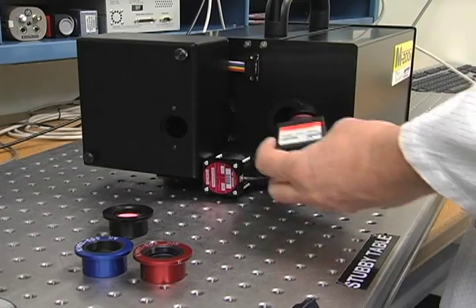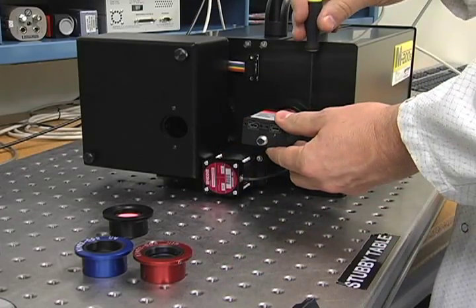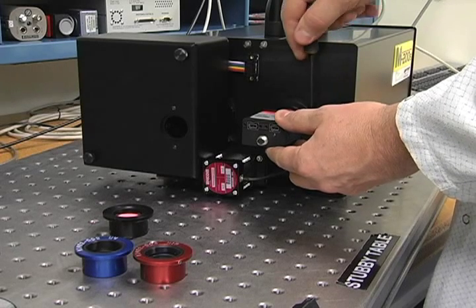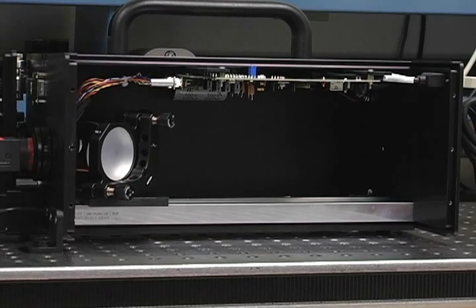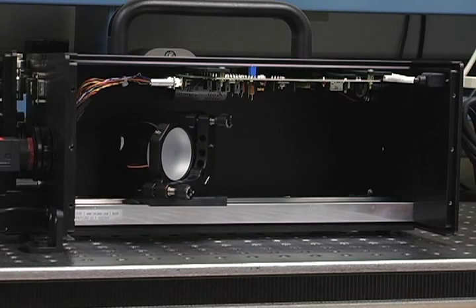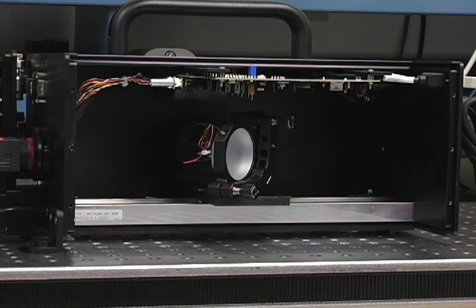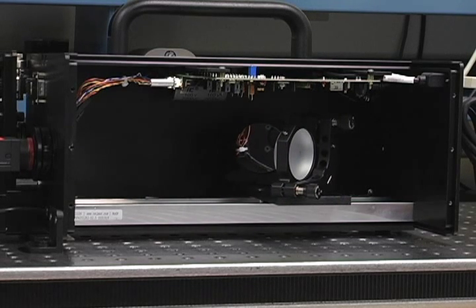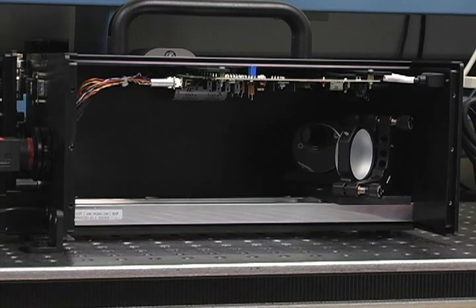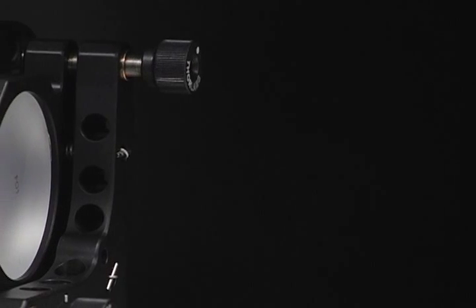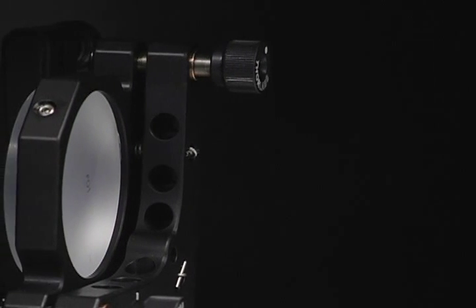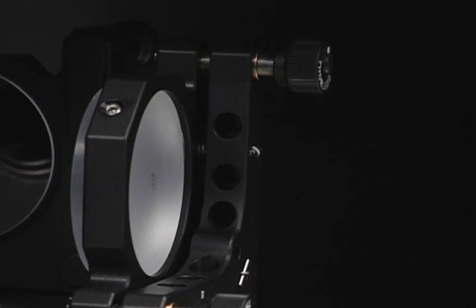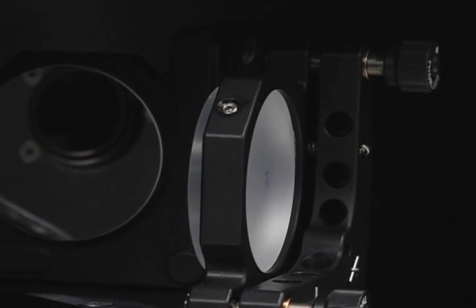The M-squared 200S optical train uses a fixed-position lens and camera with a moving stage which changes the beam's camera path length, allowing the instrument to measure the beam diameter at precise distances from the lens. The M-squared system automatically translates the camera through the beam's waist to measure where the beam focuses and how it diverges.